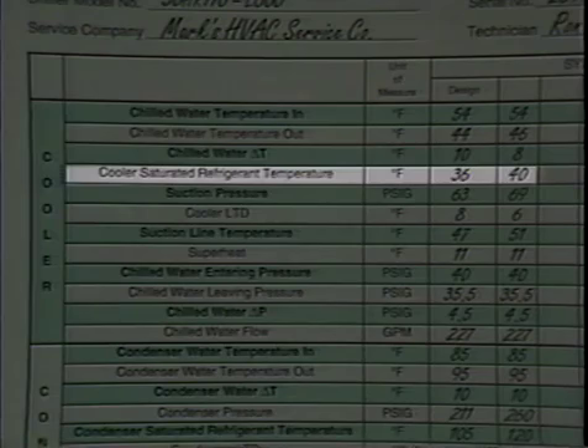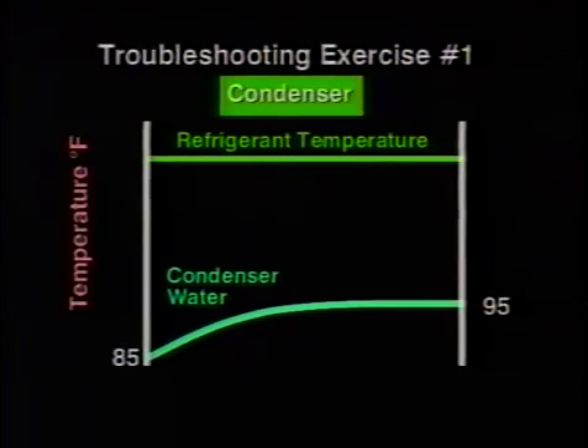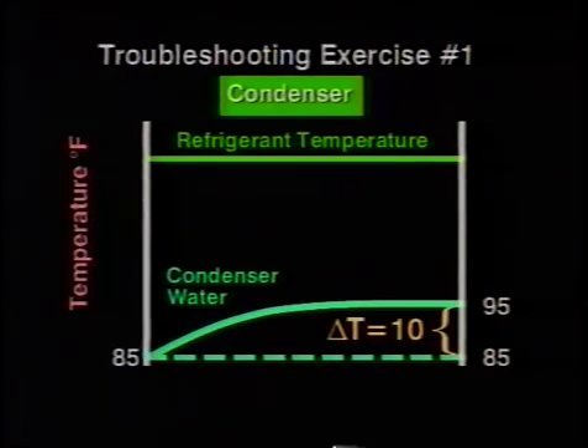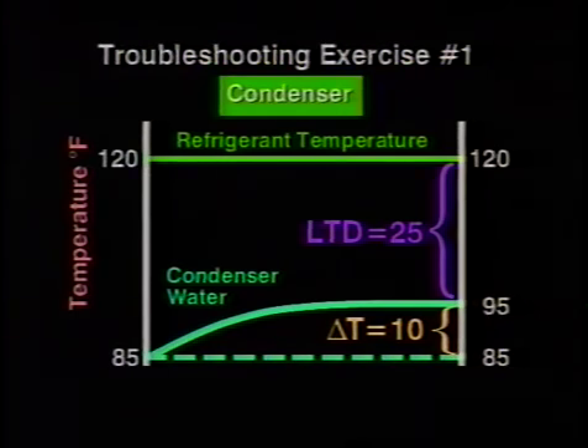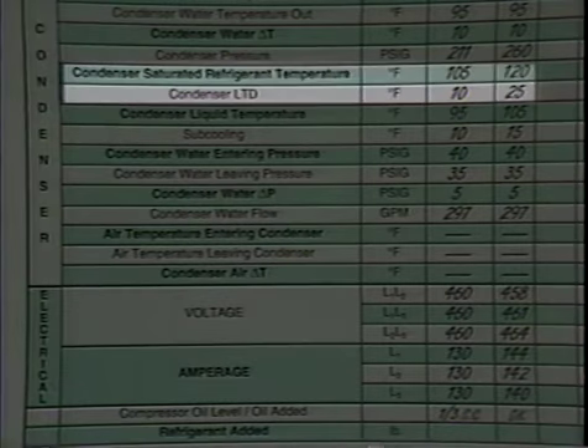Saturated cooler refrigerant temperature is high, but superheat is normal, so the expansion device is doing its job. The condenser water in is 85 degrees Fahrenheit and is leaving at 95 degrees for a normal rise of 10 degrees. The saturated condensing temperature is 120 degrees instead of the design 105 degrees, and our LTD is high at 25 degrees, indicating resistance to heat transfer. Since both the LTD and the saturated condensing temperature are high, it appears that the condenser is the problem.